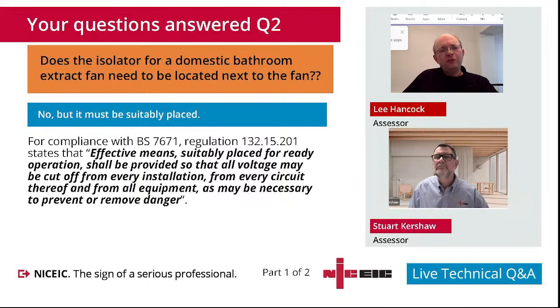In certain situations, though, the fan isolator might be remote. It could be in a cupboard on a landing, something like that. And where it's not obvious what the isolator is controlling, we need to mark the isolator with a durable label. So it may not be a switch that you operate all the time, but the user's aware that it's there and what its purpose is. So if there is a situation where we need to isolate the fan quickly, they would know through experience of the layout of the building where to head for this and how to switch it off.